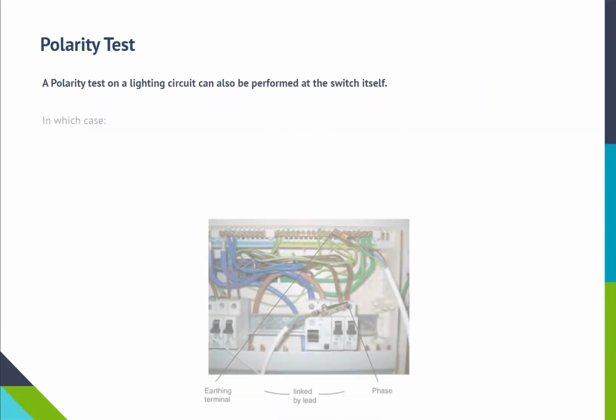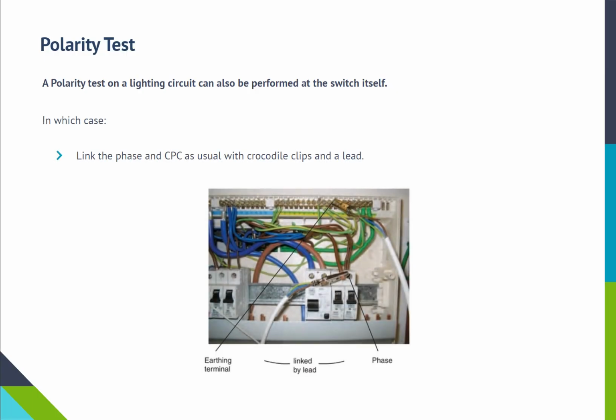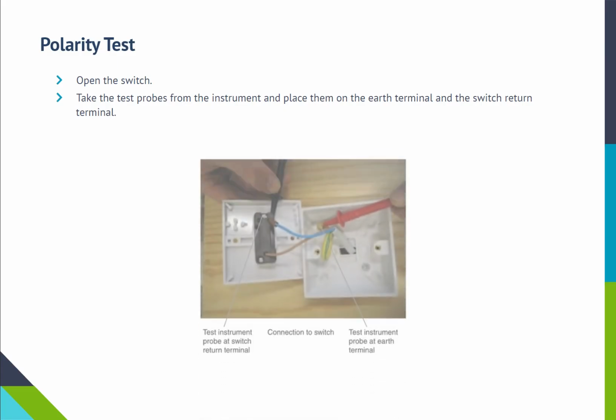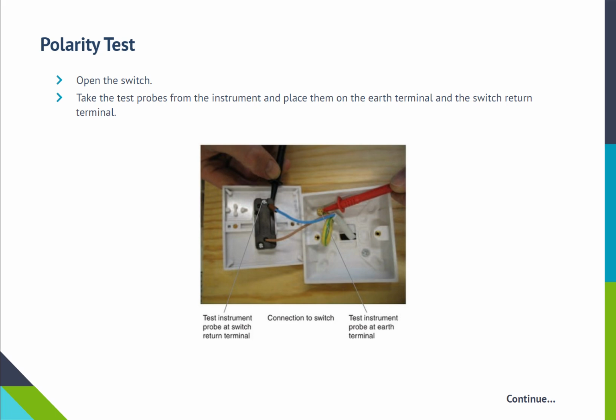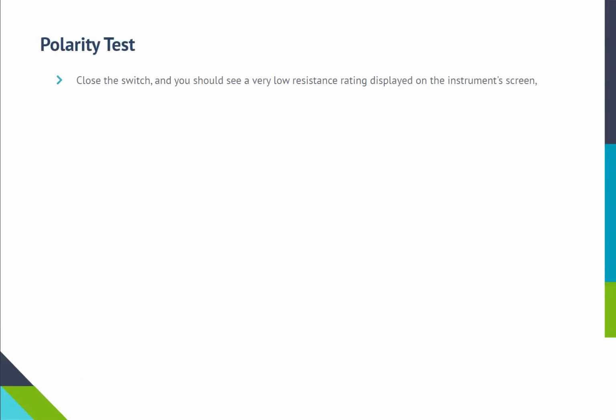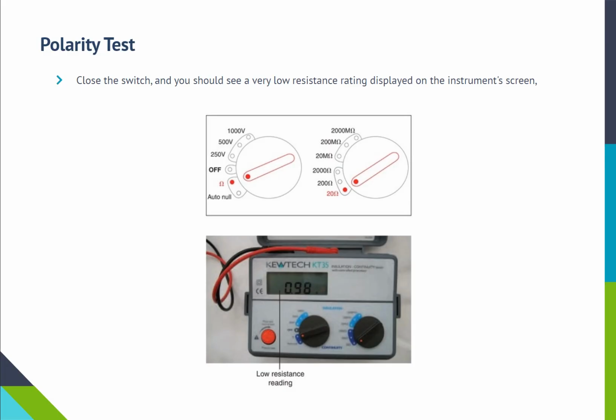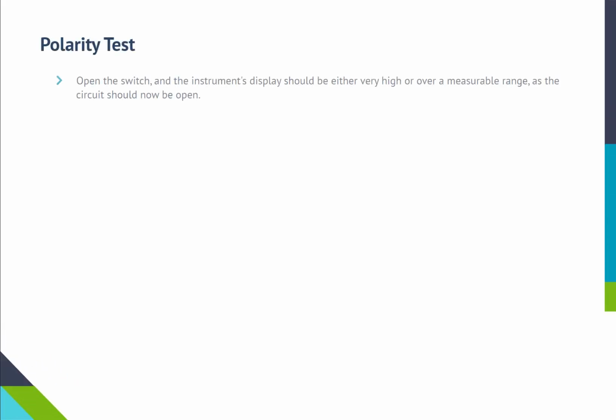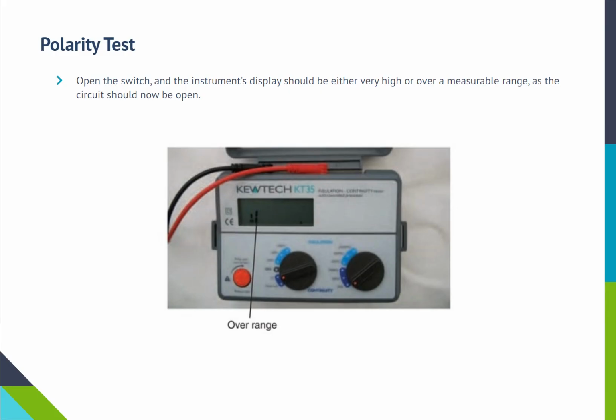A polarity test on a lighting circuit can also be performed at the switch itself, in which case, link the phase and CPC as usual with crocodile clips and a lead. Open the switch. Take the test probes from the instrument and place them on the earth terminal and the switch return terminal. Close the switch and you should see a very low resistance rating displayed on the instrument's screen. Open the switch and the instrument's display should be either very high or over a measurable range, as the circuit should now be open.